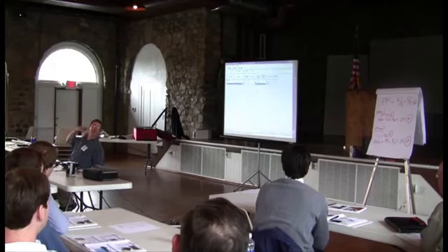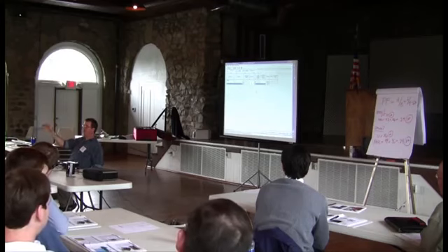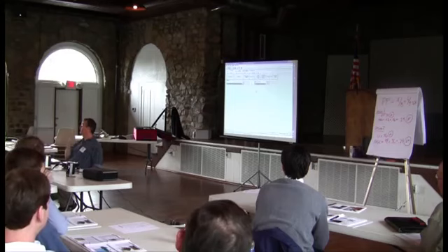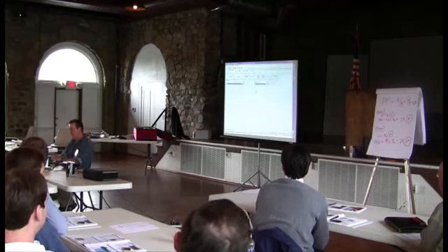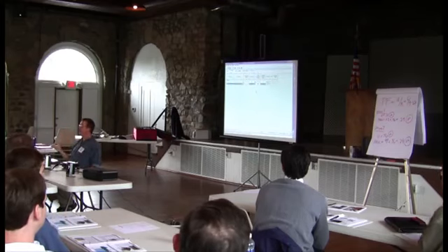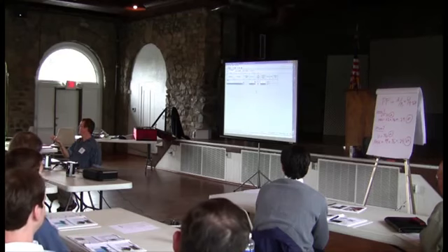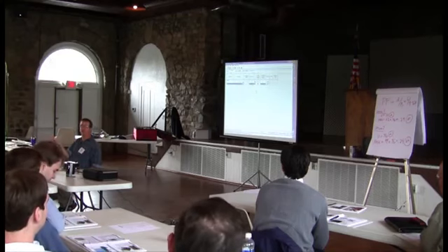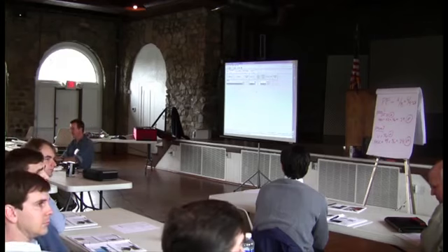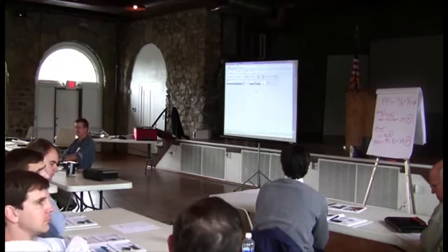And what's the perimeter of this building? It's 50 and 70. Help me. 50 and 70 is 120, and then 240 feet around the building, right? And we're going to use a 10-foot wall. So 240 times 10 is 2,400. That's the gross wall area. Gross wall is different from, what does gross wall include? The glazing and the doors, right? So not net wall. You put the gross wall in. It'll do the math. The key point on that, though, is remember it needs to be the gross wall area of your envelope. So if you've got a parapet wall, you do not add that.